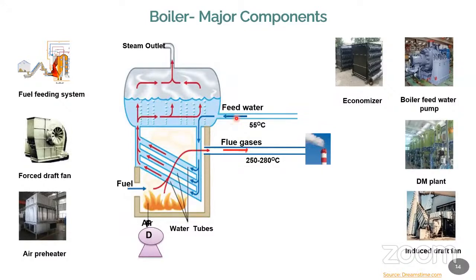I install it. So either I can use a fire tube boiler or a water tube boiler. This is an example of a water tube boiler where the feed water comes here and goes into the tubes. Here we have a fire, and the fire will produce the necessary heat, and that heat is transferred to the water. Because of getting the heat, the water will become steam, and the steam will go to the process. Now one by one we will discuss.